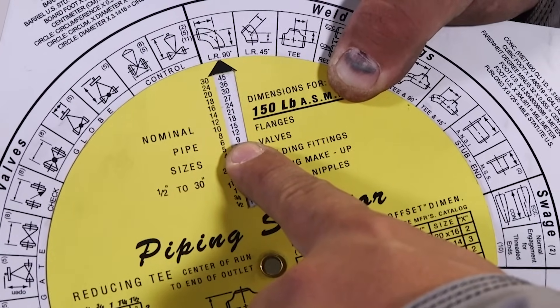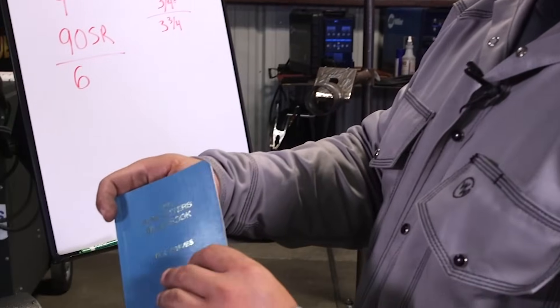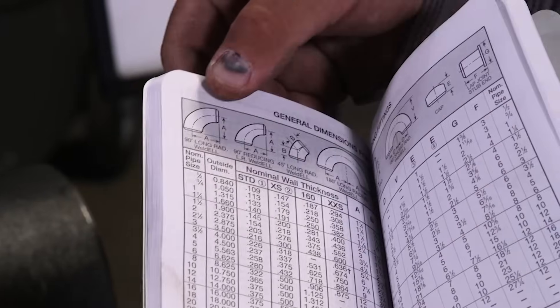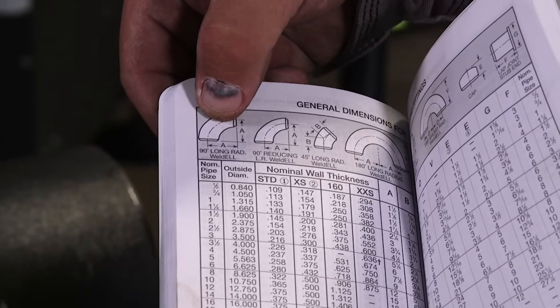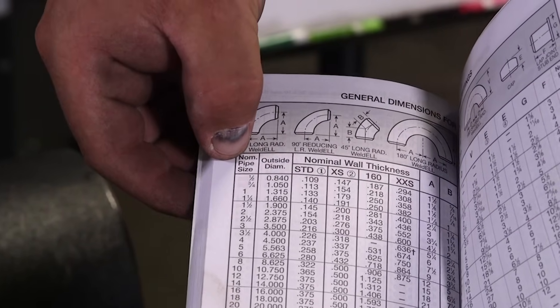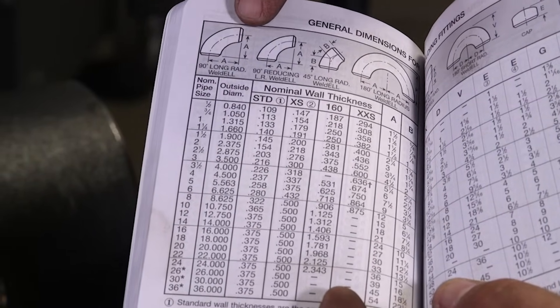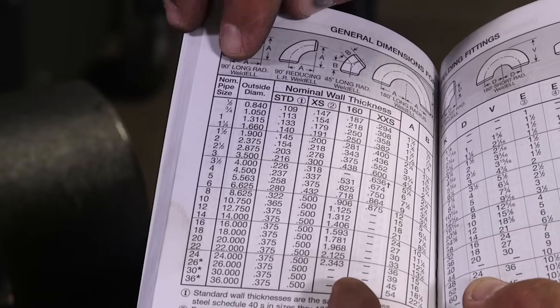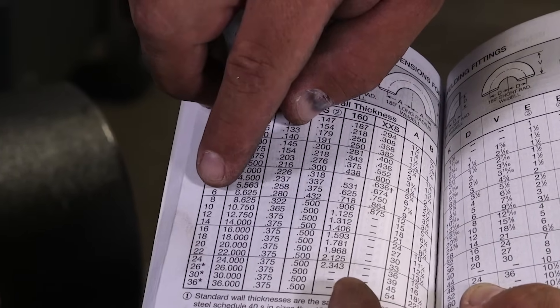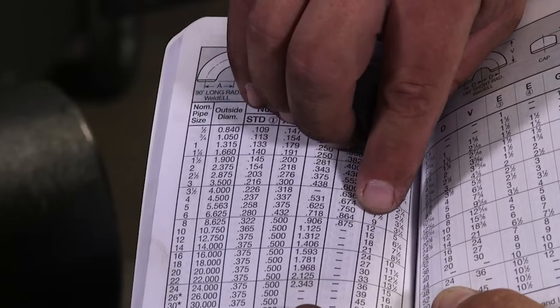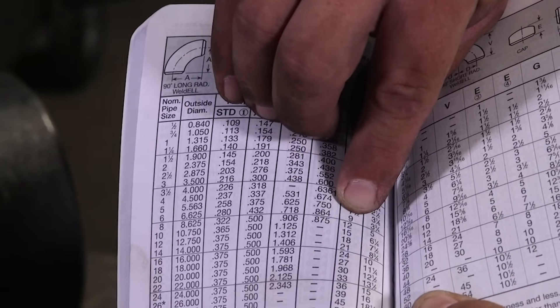Alright guys, so on this pipe fitter blue book, you turn to page 95. You can see here, again we have our long radius 90. You go right here to nominal pipe size, you go down to 6. You can see on our drawing here, it says to go to A to get our takeoff. You can go all the way down until you get to A. It's also 9 inches.